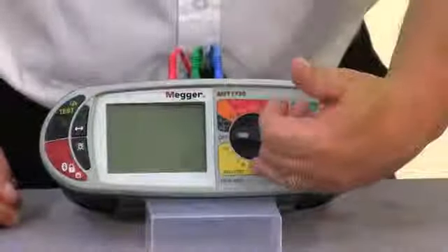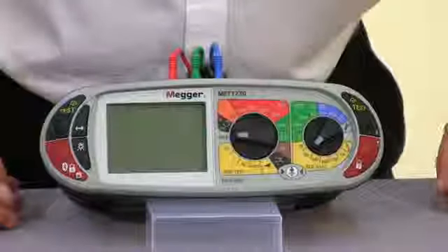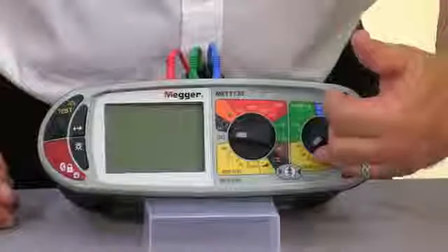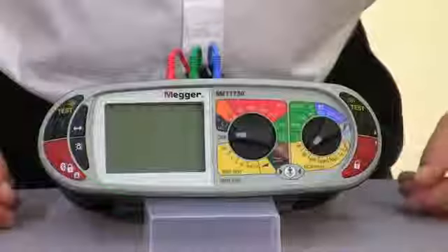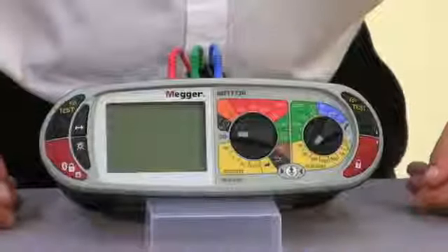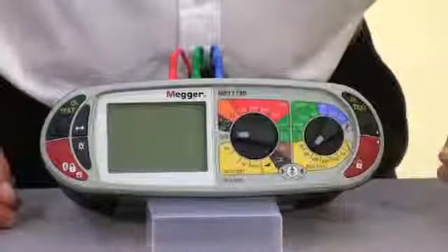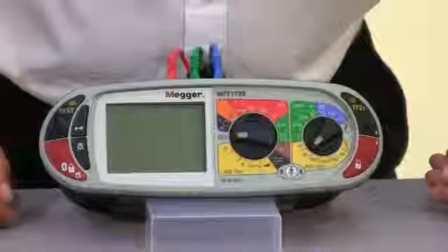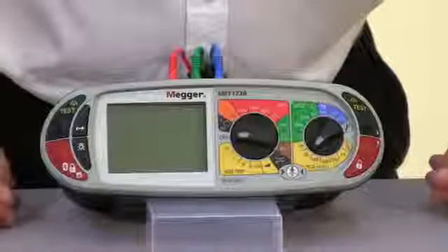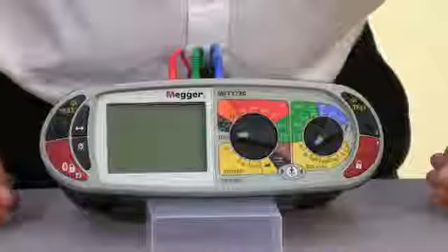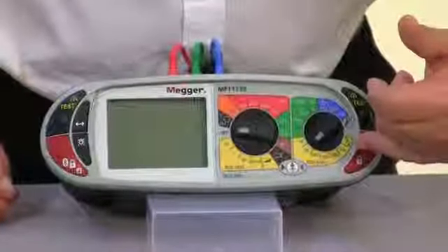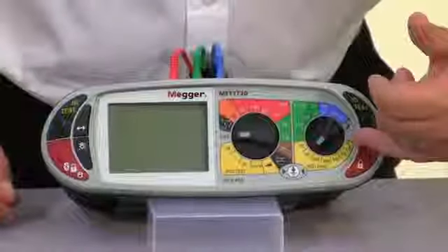We also have the auto test facility where we can dial up the rated value of the RCD, start the auto test, and it will run through the whole sequence. And then the ramp test, and this is particularly useful when fault finding because it will prove at exactly what value an RCD will operate. We also have our variable RCD, which I shall show you shortly.